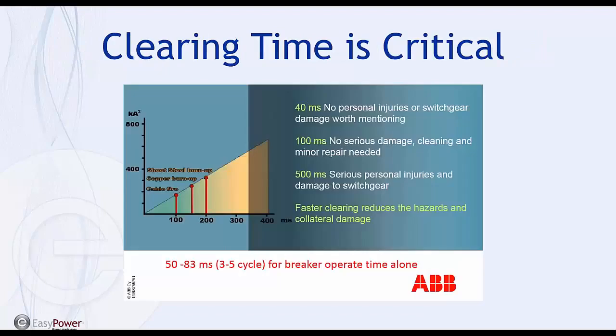So anyway, the main strategy is fast clearing times. That's absolutely what's critical. And you can see here that in half a second we have serious personal injuries and extensive damage, and actually it looks like it occurs a little bit before that based on this slide. It's 100 milliseconds where you can get into a little bit of damage. Now, of course, if that arcing fault current is high enough, you're going to have damage at that time as well. So when you look at the average time it takes a breaker to operate, 3 to 5 cycles, or 50 to 83 milliseconds, you're pretty close to this 100 milliseconds already. You don't have a lot of time for the arc flash relay to operate and quench the arc. So time is of the essence, time is critical, and that's what we offer.